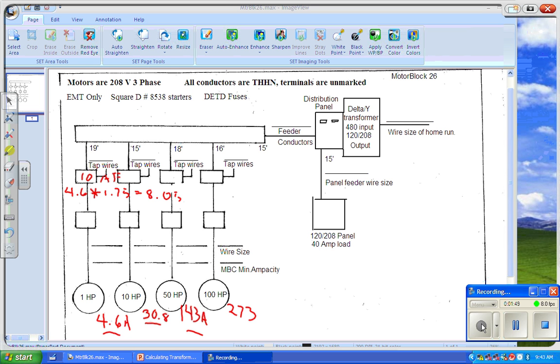In other words, if the circuit is actually coming from an outside circuit, such as a lighting circuit, where the motor branch circuit, short circuit, and ground fault protection device does not provide protection in accordance with 430.72B2, separate overcurrent protection shall be provided. The overcurrent protection shall not exceed the value specified in column A of Table 430.72B. So separate protection or separate control is column A in our Table 430.72B.